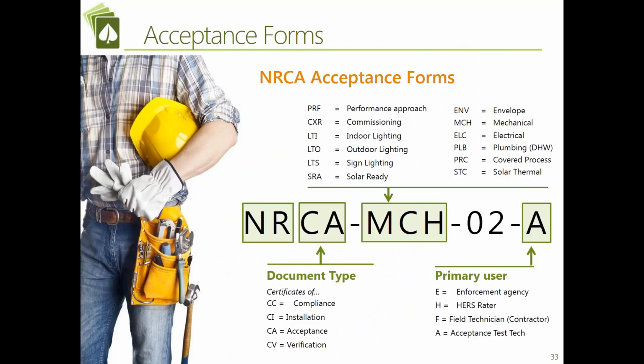So what we like to say is this acceptance test technician aspect, and there are forms associated with this that the acceptance test technician has to provide out in the field to be available to everyone, might be incorporated into the functional testing requirements that are triggered when that conditioned space is greater than 10,000 square feet. This acceptance testing for California requirements and all of these forms are happening all the time. When is acceptance testing triggered for California? Well, it's required for all lighting controls, and it's required for all mechanical control features also. Currently, that acceptance test technician for controls is a specifically trained and certified acceptance test technician by a provider. It can still be the installing contractor, does not need to be third party, but they have to go through some additional training on how to test those controls to California Energy Commission's criteria.